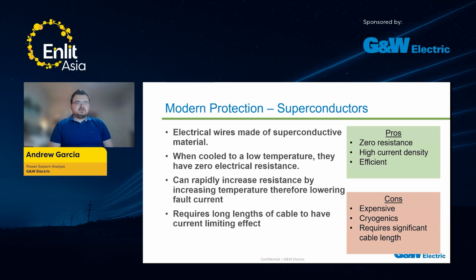So pros: very good, zero resistance or near zero resistance, so no power losses or minimal power losses across that length of cable. High current density: basically there's no electrical resistance, so there's a much lower hazard in passing a large amount of current through these wires, and highly efficient as a result. You need to install fewer of these wires to have the same effect as a regular set of cables.